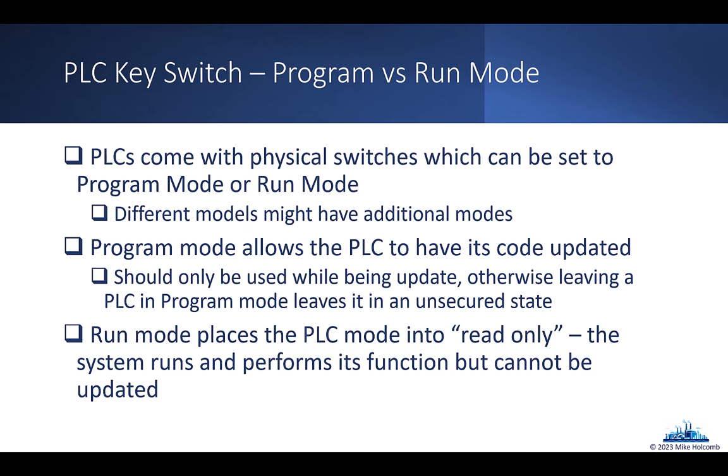That way we can control when somebody can remotely or even locally update the firmware and the programming of a PLC. From a cybersecurity perspective, if we have a PLC running in run mode, that's the read-only mode. It means the PLC is running, doing its job, and nobody can actually make changes to it. The only way you can make changes to the PLC in run mode is to change the key switch back to program mode. If it's in program mode, the PLC will still do its job and function, but you also have the ability to upload firmware, make changes to the code, etc.